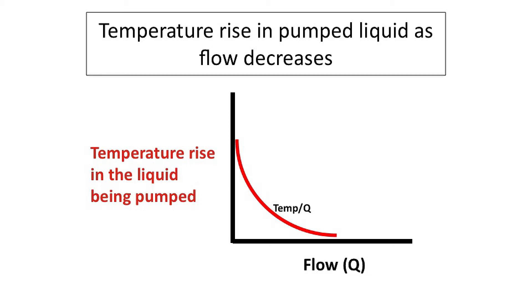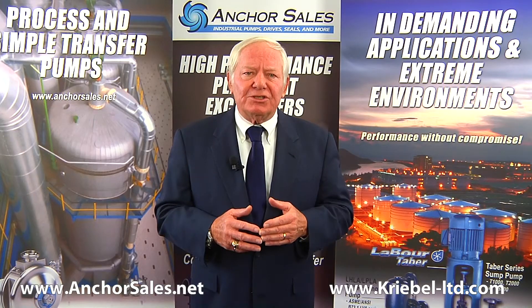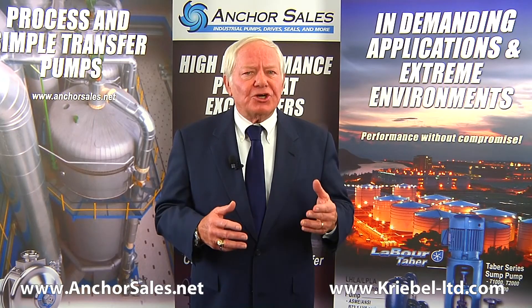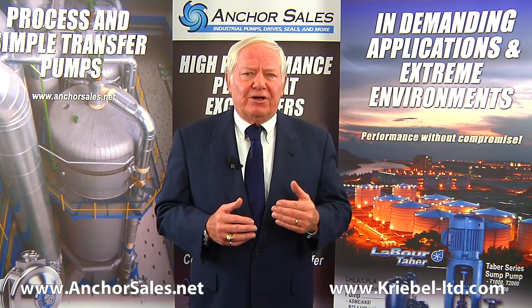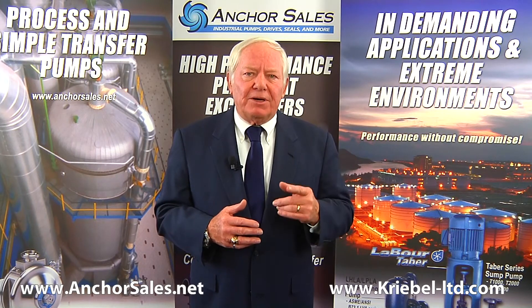There is a point where the temperature rise will cause damage to the pump. The pump can never be run for any length of time below this point. Other minimum flow restrictions, which occur at a higher flow, could be set by the pump design.